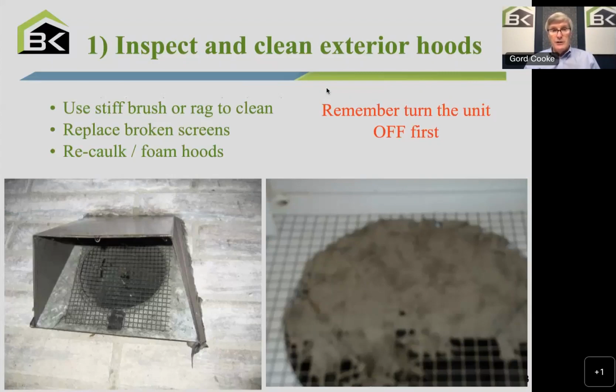So we want to look outside, and it's a little bit inconvenient. You have to look down. You want the unit turned off because when you go to brush this off, you don't want that debris being sucked back into the unit. So a stiff brush or a rag, just wipe it down. Just make sure it's the screen. And of course, that screen is to keep out rodents and birds and so on. And so you'd want to check to make sure the screen is intact.